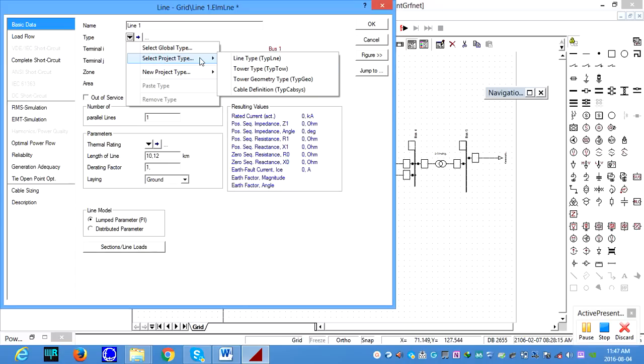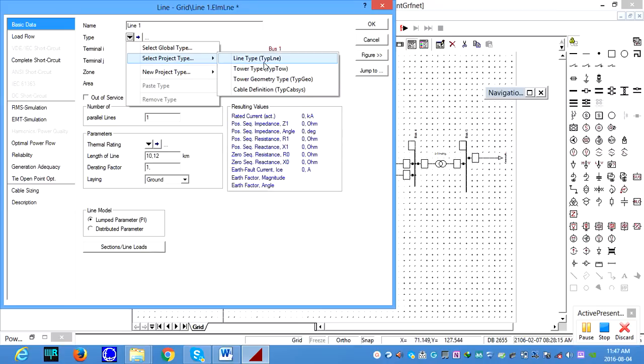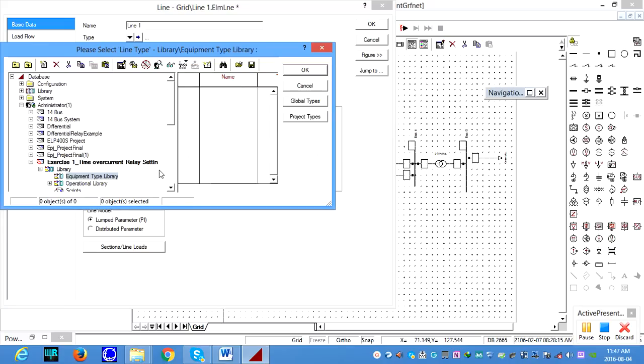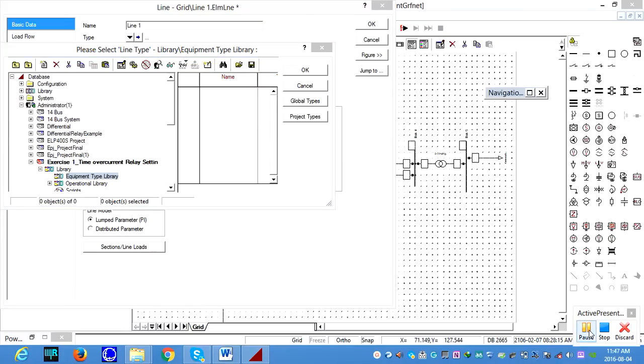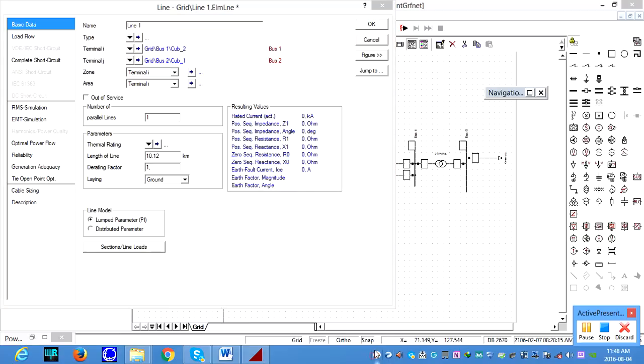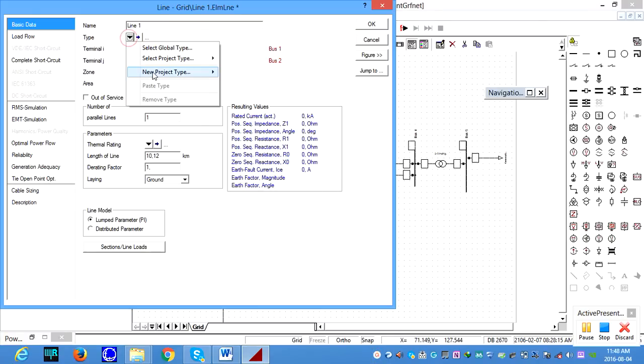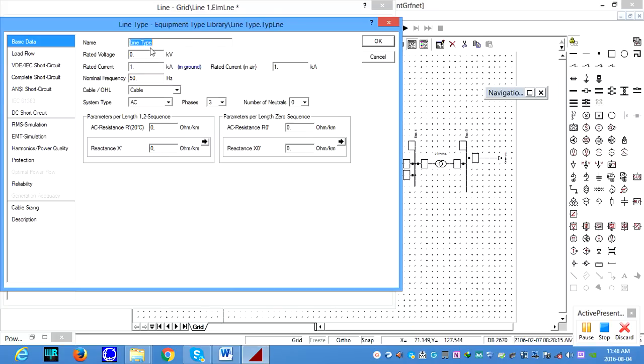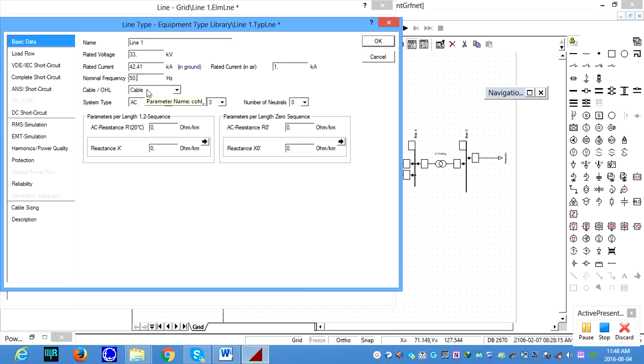We can go for the project. And we can select the line type. The first one. Okay. Now we need to set the line type. Go to a new project. Line type. And let's name it as line 1. And the rated voltage supposed to be 33 kV. And the current rating supposed to be 42.41 kiloamps. 50 Hz frequency. It's a cable.